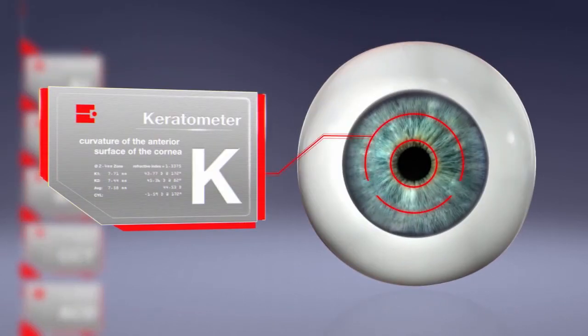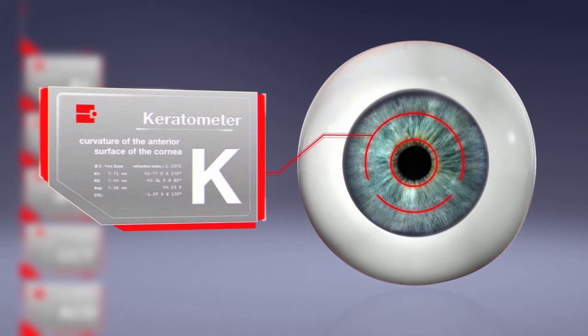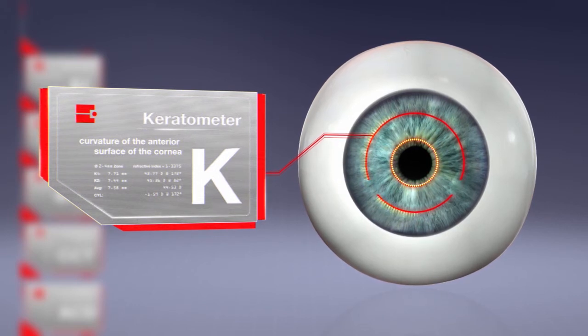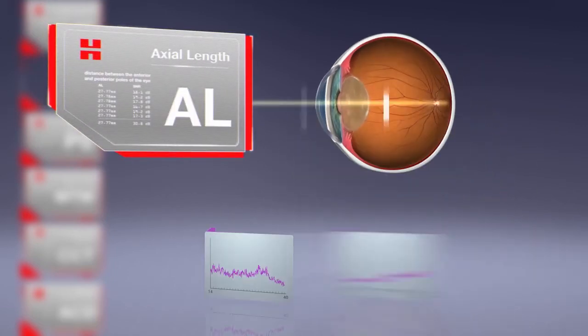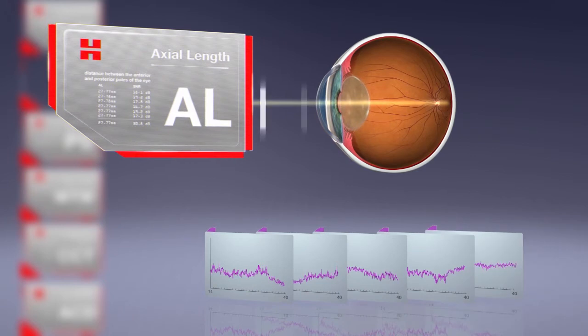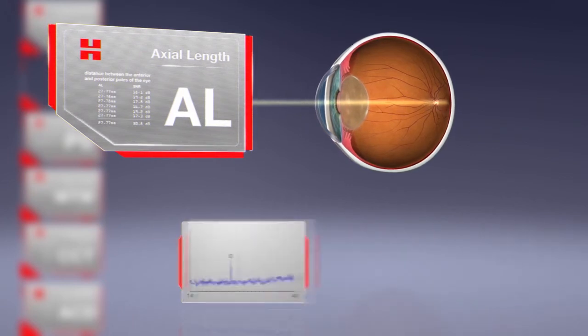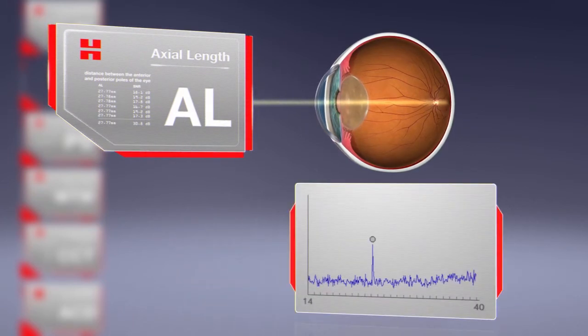The AL scan offers highly accurate keratometry measurements with a maximum of 360 data points in each of two rings. Even through dense cataracts, axial length can be measured by taking multiple readings and averaging those readings using advanced algorithms which enhance the signal-to-noise ratio.